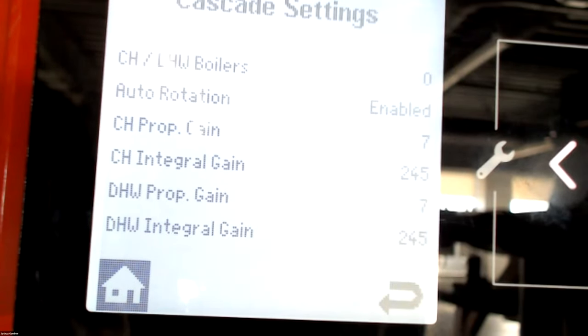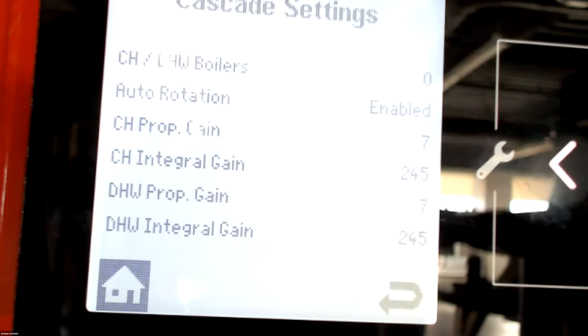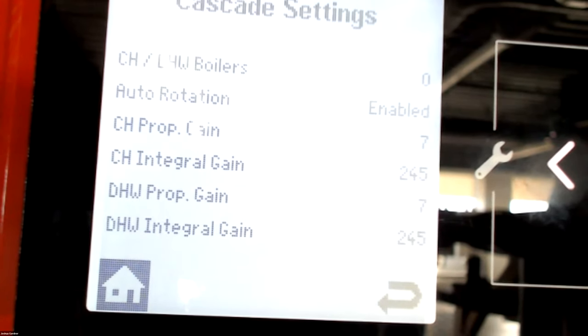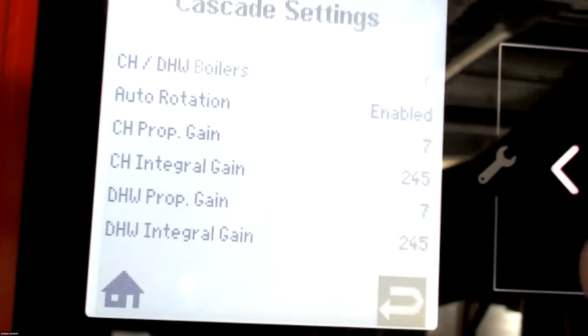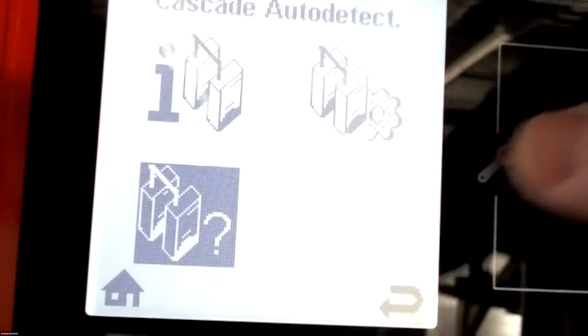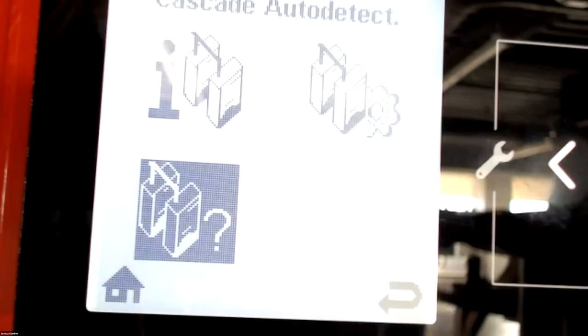So if your boiler is overshooting, this is where we could go in and adjust those settings to slow or increase our firing rates. But again, if you do need to do that, first thing we're going to recommend is installing your system sensor in the immersion well. And if that is, and we're still overshooting, that's when we'll go in and adjust those. Also, if we make any changes in our cascading settings, we got to go back through and auto detect. So I'm not going to hit this because it's going to go through a whole detection and it's going to take like 3 minutes. But we'd click on this right here.